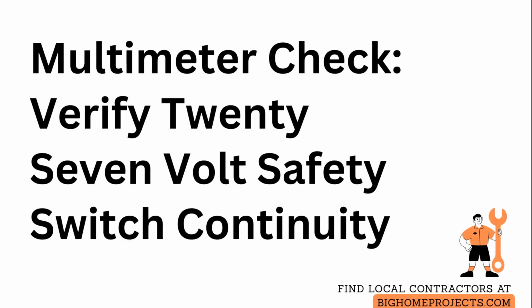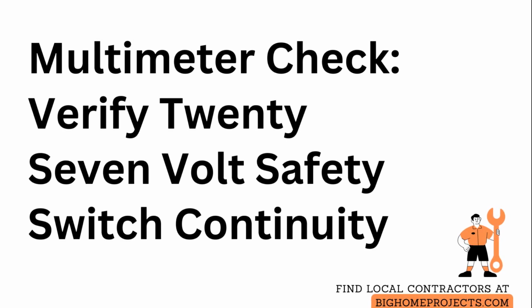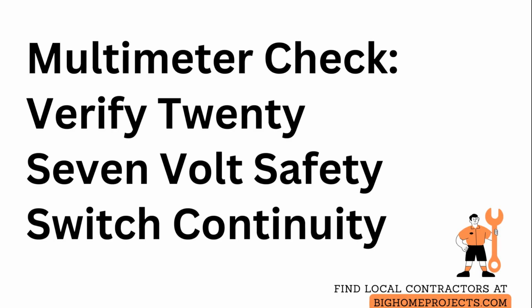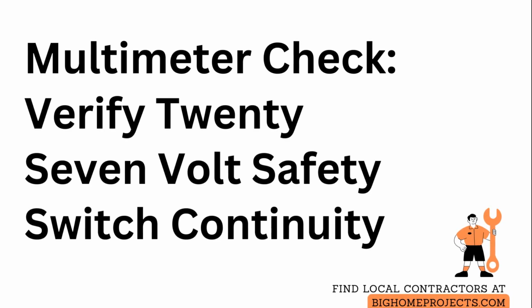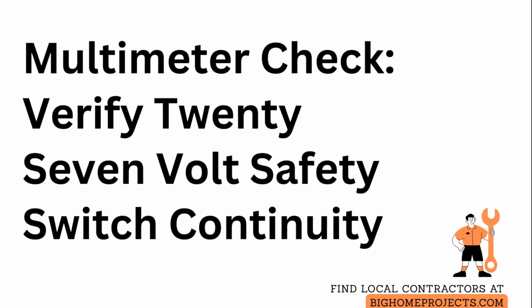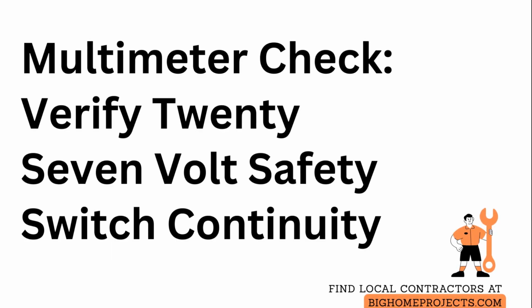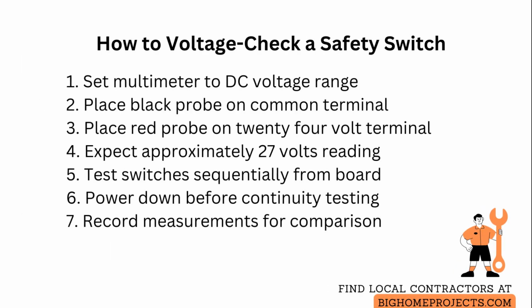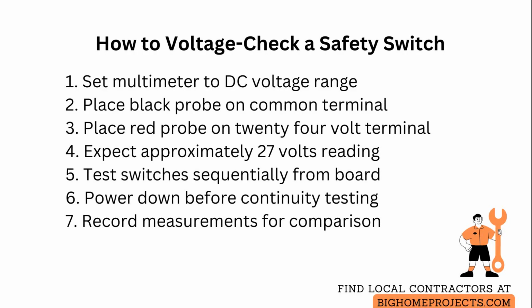Use a multimeter set to measure voltage to determine if a safety switch is open by checking for the expected 27 volts between the common terminal and the 24-volt terminal on the control board. Set your digital multimeter to the direct current voltage range that covers 30 volts direct current.